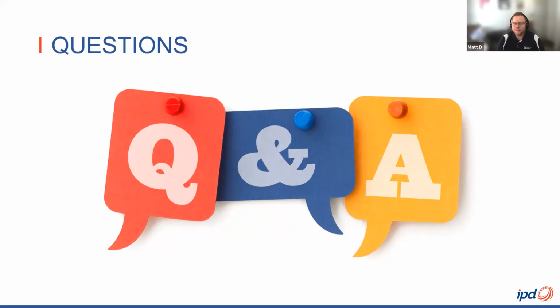Yep. Excellent. Looks like our final question in here for the moment. Can we provide some field situations where a Type A is still applicable? I would think the only one really in this situation is for existing circuits that are already installed. They can stay installed. Referring back to that new ERAC document that's available, one that probably falls into a little bit of a gap here is where an AC type has been installed prior to the 1st of May in a new construction build, but the circuit's not yet energized. It's discussing that as long as it's been installed and certified, you've done your certificates of test, and the equipment's signed off, they can still stay in that instance.